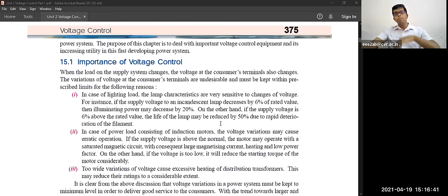Okay. In case of power load consisting of induction motors, the voltage variation may cause erratic operation. If the supply voltage is above normal, the motor may operate with a saturated magnetic circuit with a consequent large magnetizing current, heating, and low power factor. In non-peak hours, the supply voltage will sometimes go up to 240 volts, 250 volts. If you are running the motor at that time, your motor will get heated up like anything.